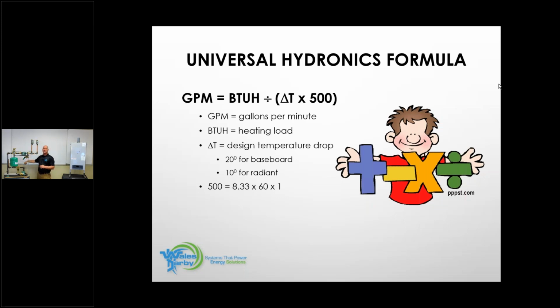It's coming back at 160. This boiler now has the ability to elevate that water back up that 20 degrees to send it reheated out of here to keep the BTU cycle going. We're producing BTU in the boiler. We're putting the BTU into the home through our heat emitters in the rooms.